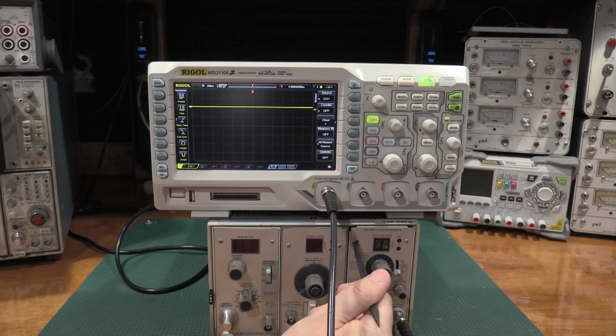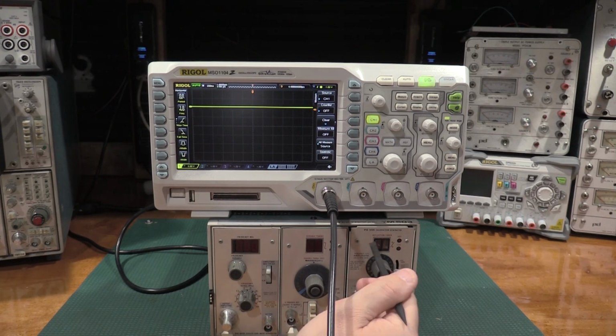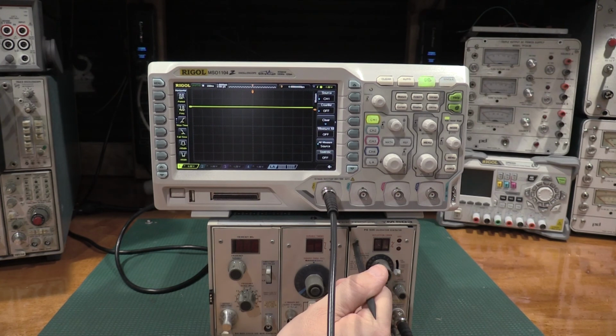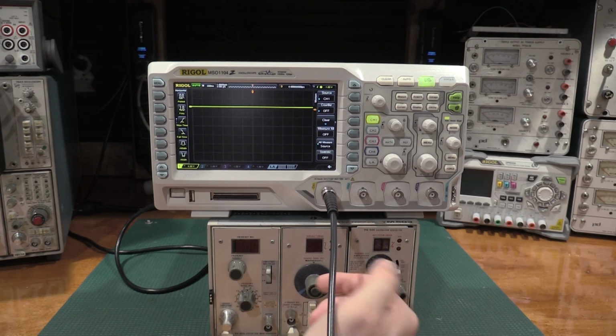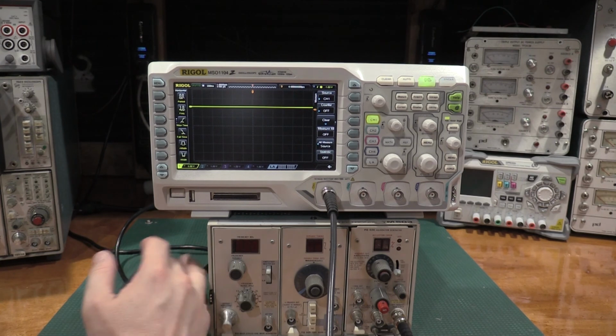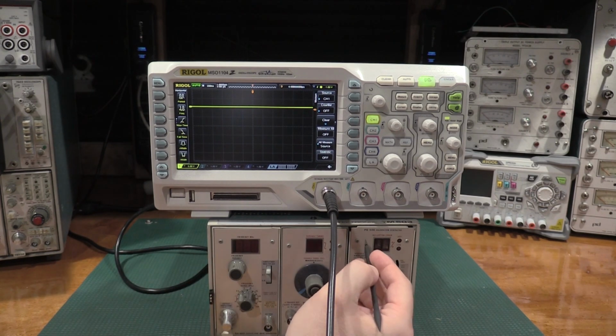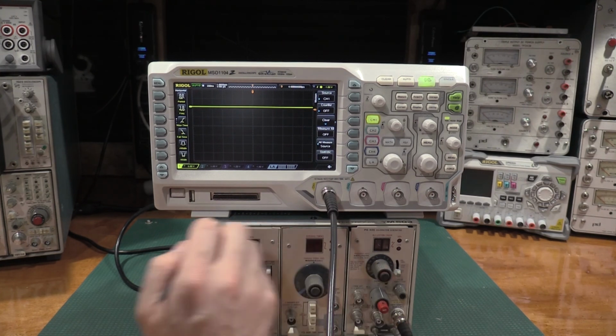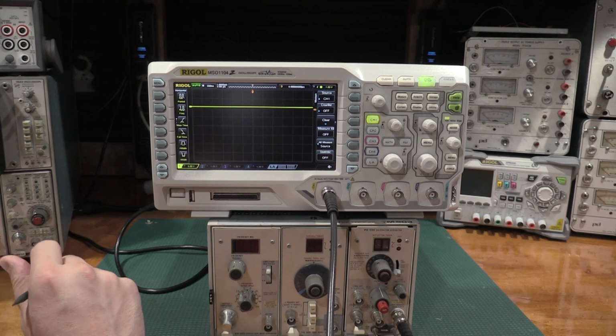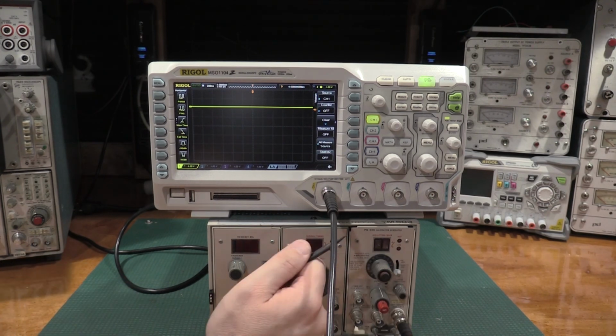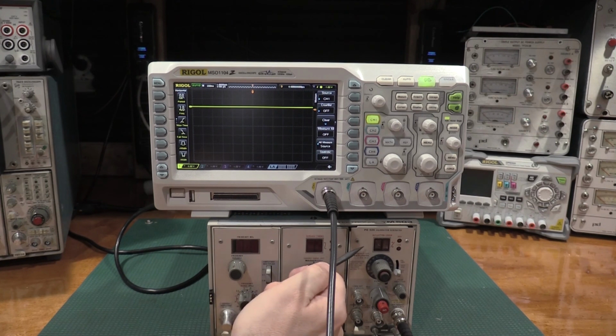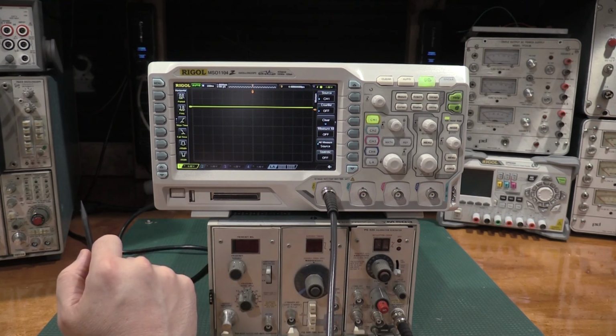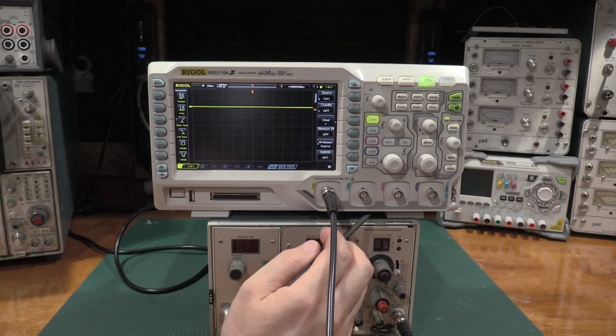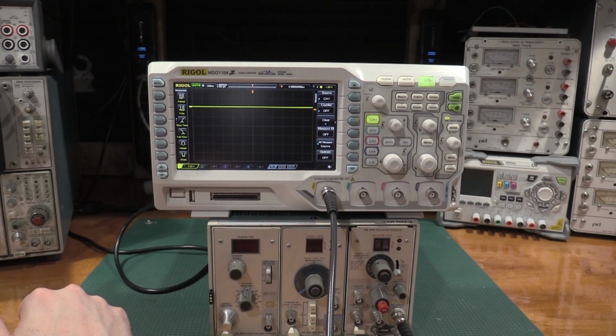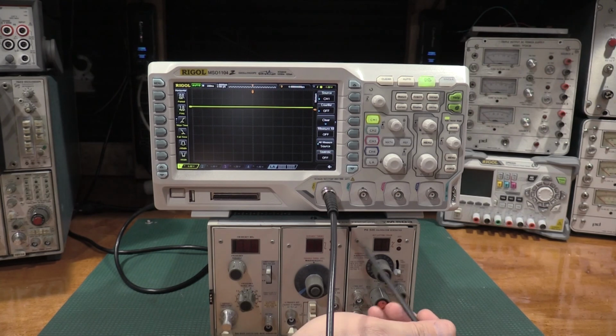If you do acquire a PG506, be really careful with it. There is a 100-volt switching supply in here to generate the 100 volts from the voltages that are in the 500 frames. That transformer, if that transformer gets damaged or overheated or melted, it's going to be unobtainium to find. It's going to be a very difficult part to source and find. Definitely check the capacitors in there, especially the bulk caps. If there's a problem there, that transformer is going to get stressed. So definitely check that out if you end up with one. Also, be careful if you open one. There's 100 volts in there.